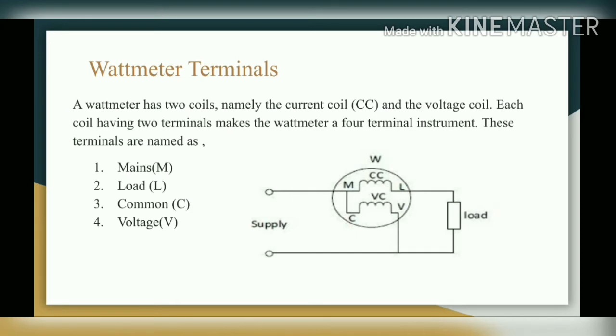Next is wattmeter terminals. A wattmeter has two coils: the current coil (CC) and the voltage coil. Each coil has two terminals, making the wattmeter a four-terminal instrument. The terminals are named Mains (M), Load (L), Common (C), and Voltage (V). M and L are the terminals of the current coil, and C and V are the terminals of the voltage coil.